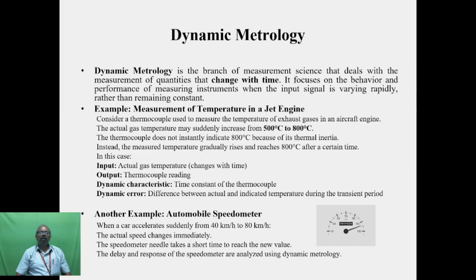Consider a thermocouple used to measure the temperature of exhaust gases in an aircraft engine. The actual gas temperature may suddenly increase from 500 to 800 degrees centigrade, but the thermocouple does not instantly indicate 800 degrees due to thermal inertia. Instead, the measured temperature gradually rises and reaches 800 degrees after a certain time.